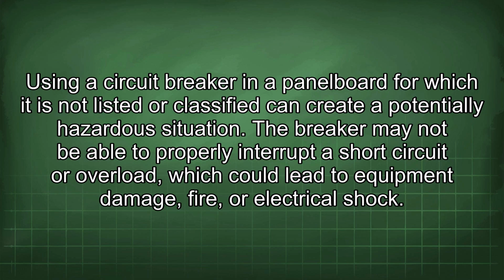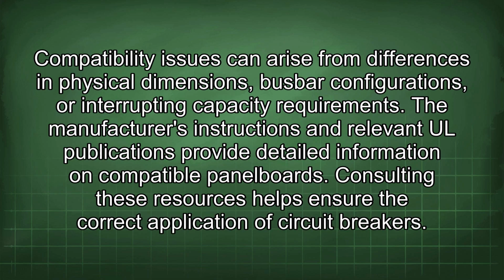Using a circuit breaker in a panel board for which it is not listed or classified can create a potentially hazardous situation. The breaker may not be able to properly interrupt a short circuit or overload, which could lead to equipment damage, fire, or electrical shock. Compatibility issues can arise from differences in physical dimensions, busbar configurations, or interrupting capacity requirements. The manufacturer's instructions and relevant UL publications provide detailed information on compatible panel boards. Consulting these resources helps ensure the correct application of circuit breakers.